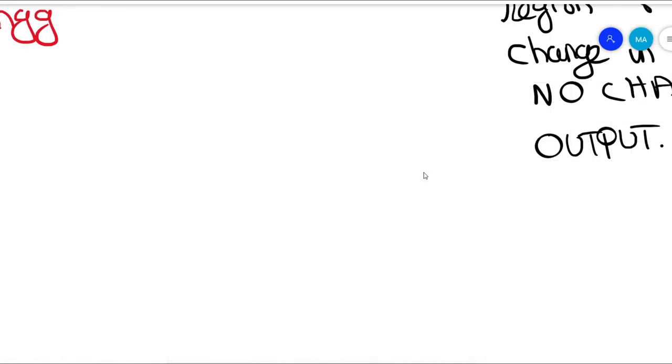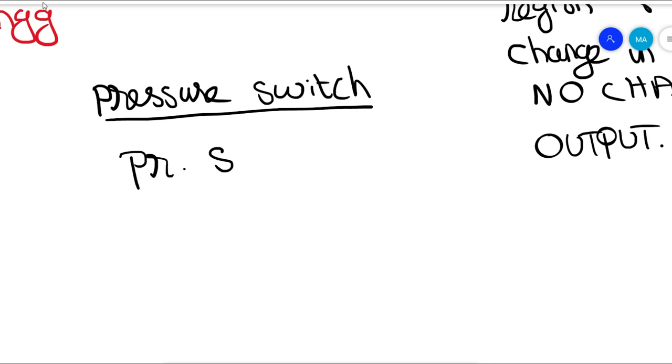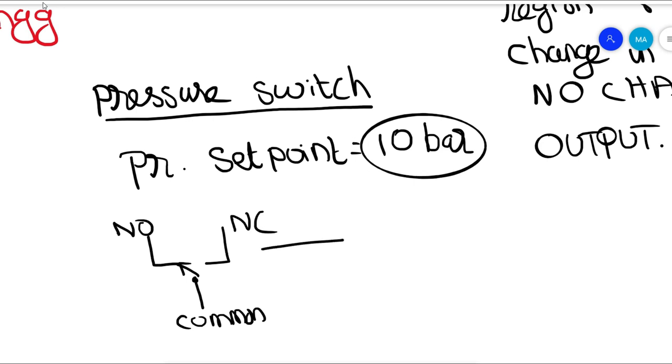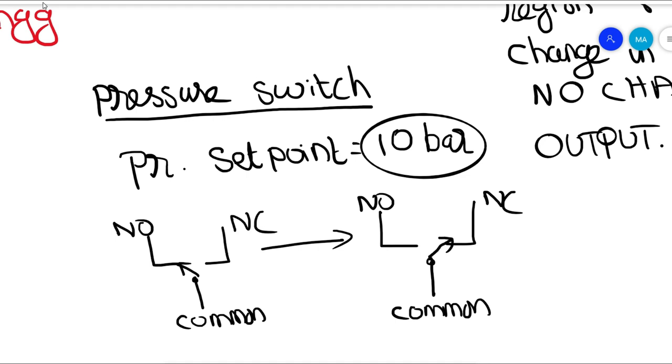Before that let's see how does a pressure switch work. So in a pressure switch, you set pressure at 10 bar. In normal condition a pressure switch is in NO contact, that is basically a normally open contact. When the process pressure increases and achieves 10 bar pressure, the pressure switch will actuate by changing the contact to normally close contact, NC contact.